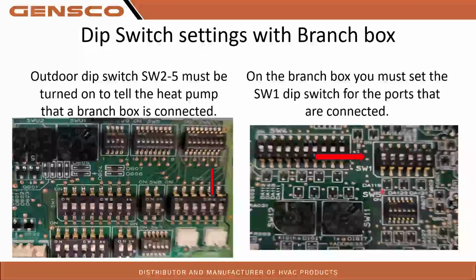Some of the older equipment, you'd be okay if those weren't turned on. May have some performance problems, but the system will still work. With the newer generation equipment, what we're finding is that if these switches are turned off, it turns off that communication to that indoor head. So if you guys are doing a startup and you're having a communication fault on indoor equipment and you have a branch box, check these switches, make sure that they're actually turned on and nobody forgot about them. It's a pretty common one for us.